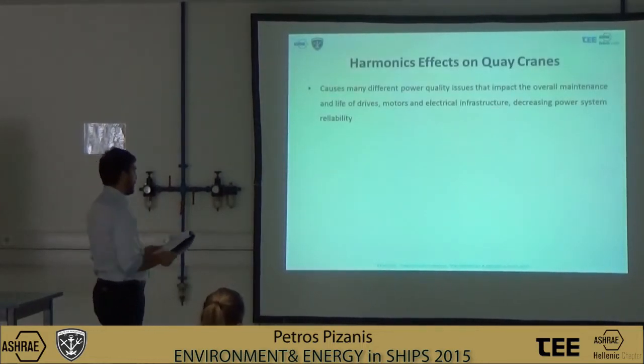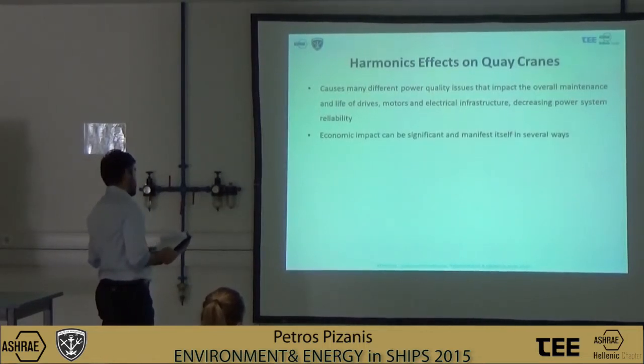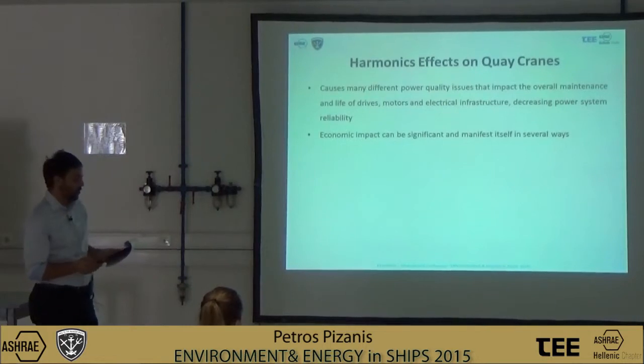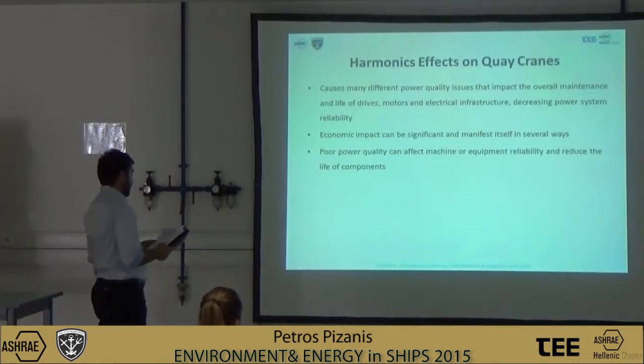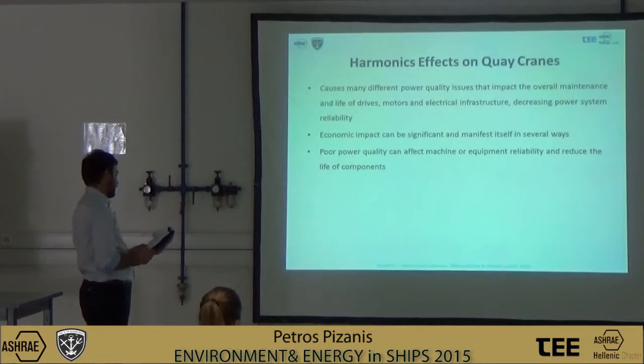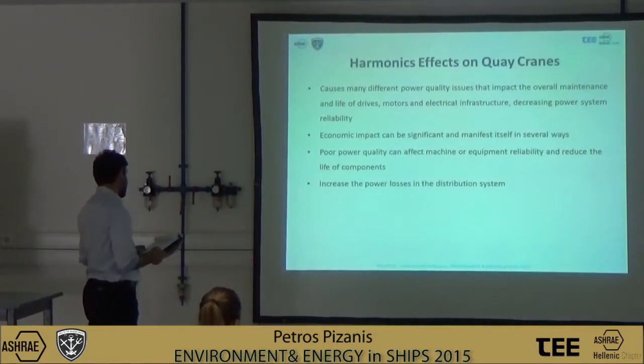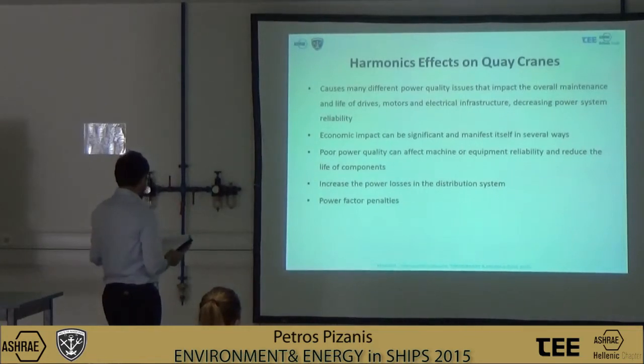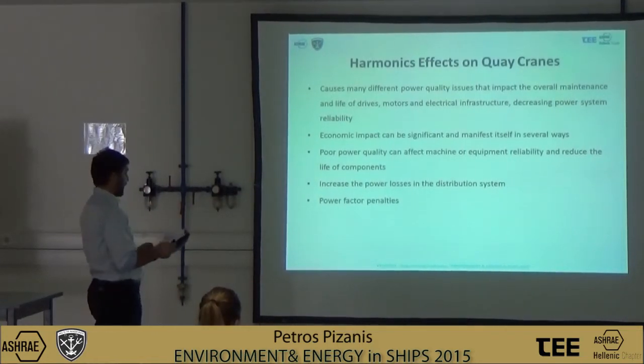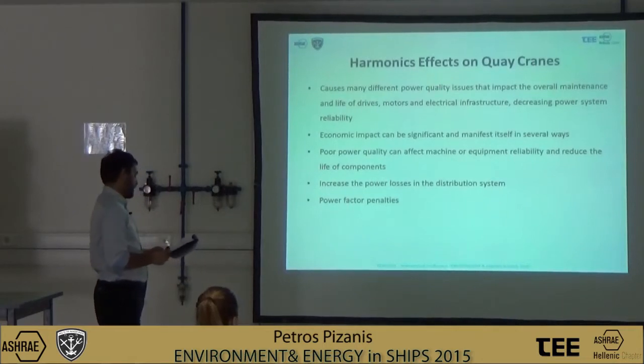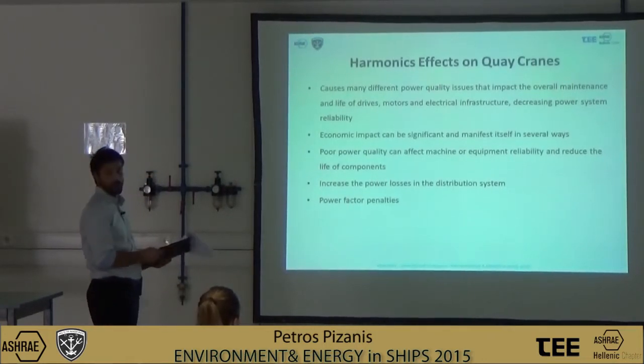Now, these distortions of electrical power in this system cause harmonic fluctuations of voltage and current, known also as non-linear load. These deformations cause many problems to the electromechanical system as well as to the environment. They cause stress on electrical circuits, electrical equipment such as relays and conductors, main power supplies, and even transformers. They also cause electromagnetic interference in electronic circuits and systems such as PLCs. Furthermore, harmonics cause economic problems, as a system which has harmonic fluctuations can also affect the power factor correction, where power supply companies can impose penalties for incorrect power usage to the company using the power.